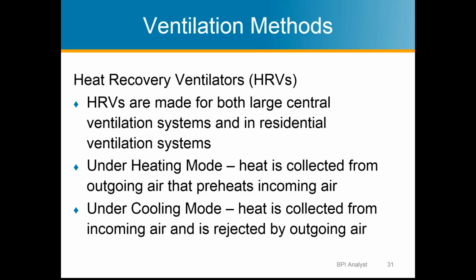So say you're in Lake Tahoe and it's 0 degrees outside. Well, that 0 degree air, instead of coming in at 0 degrees, is now able to come in at maybe 50 degrees or 40 degrees. The efficiency of these is somewhere between 50 and 80%, so you can recover quite a bit of heat through an HRV. And then under cooling mode, it just reverses. Now the air outside is really hot, and the air that you're exhausting is cooler, and the heat is transferred between those air streams, the heat, not the air itself. So it's tempering the air that's coming into the house. So you just use less heating or cooling energy through your HVAC when you have a heat recovery ventilator.